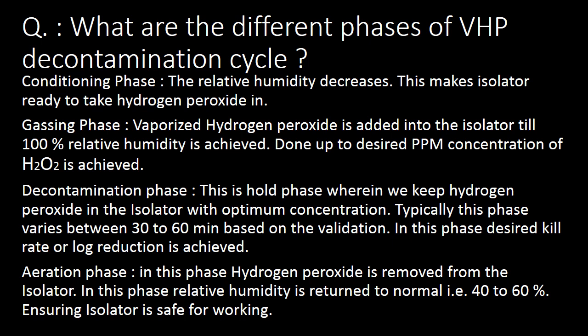The final stage is the aeration phase. In this phase, hydrogen peroxide is removed from the isolator, and relative humidity is returned to normal — that is 40 to 60% — ensuring the isolator is safe for working.